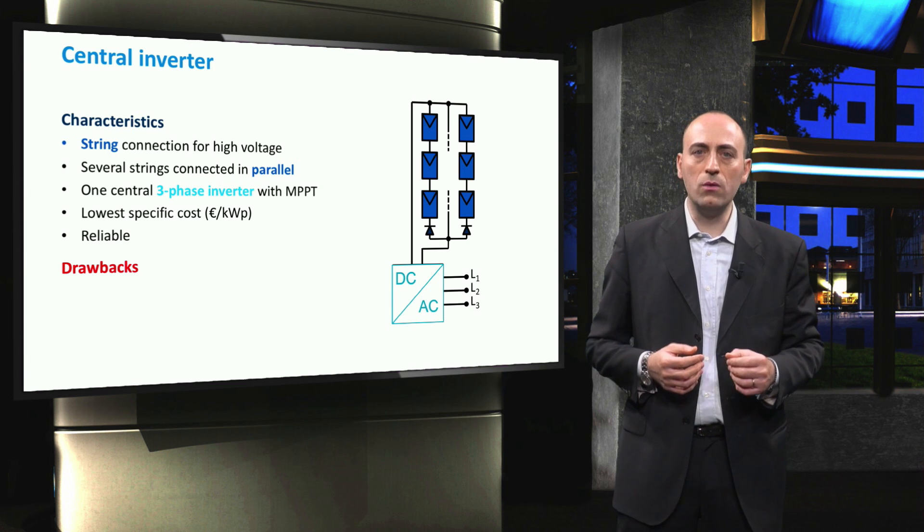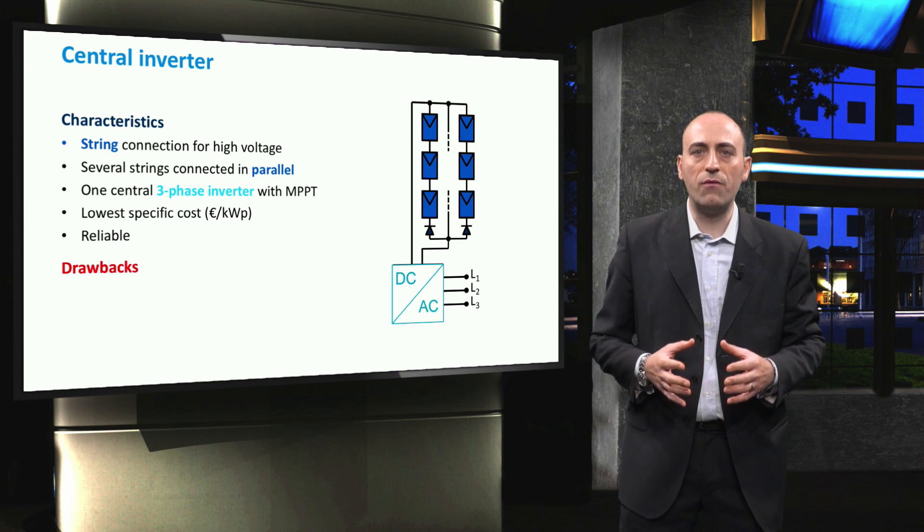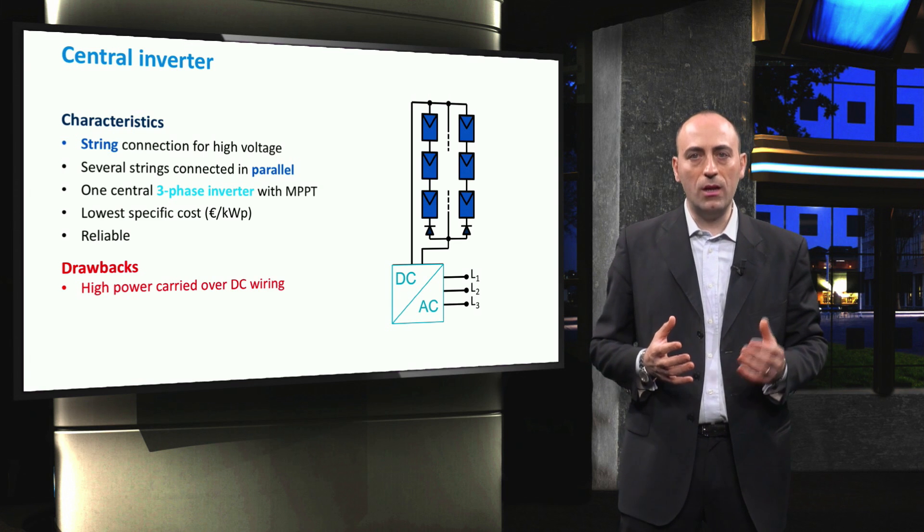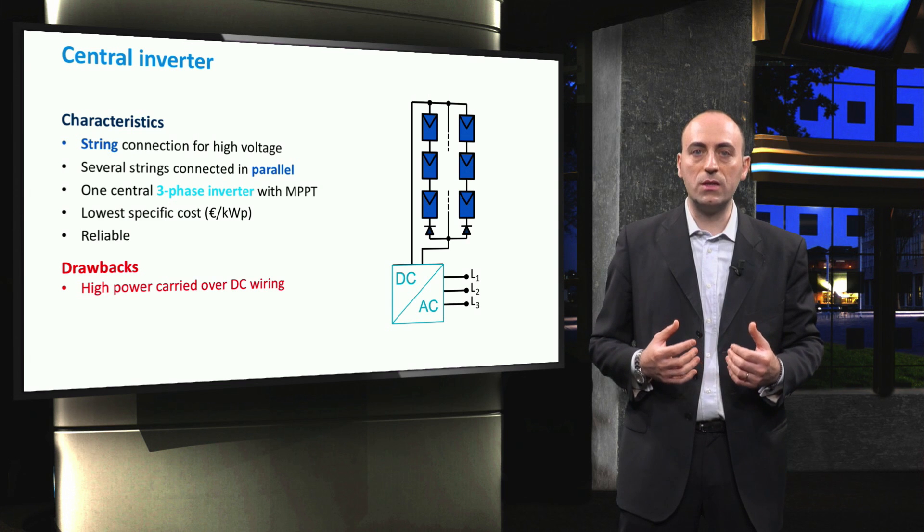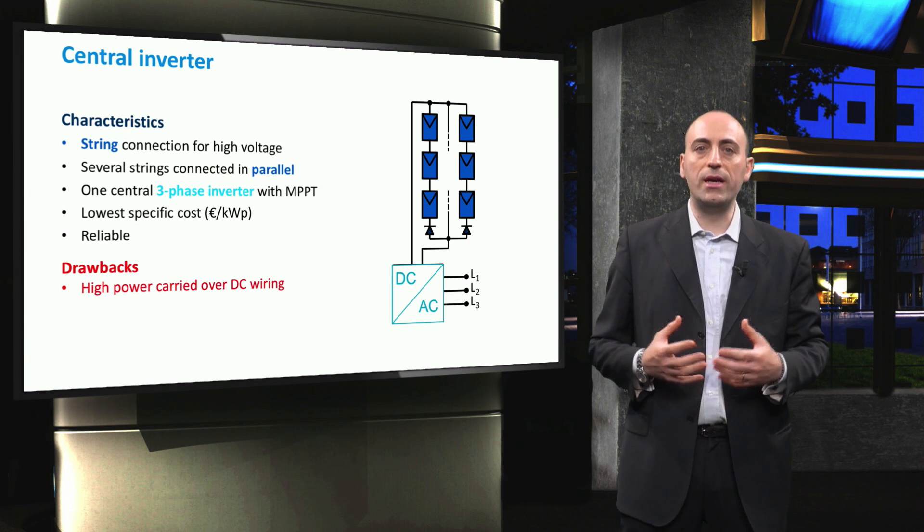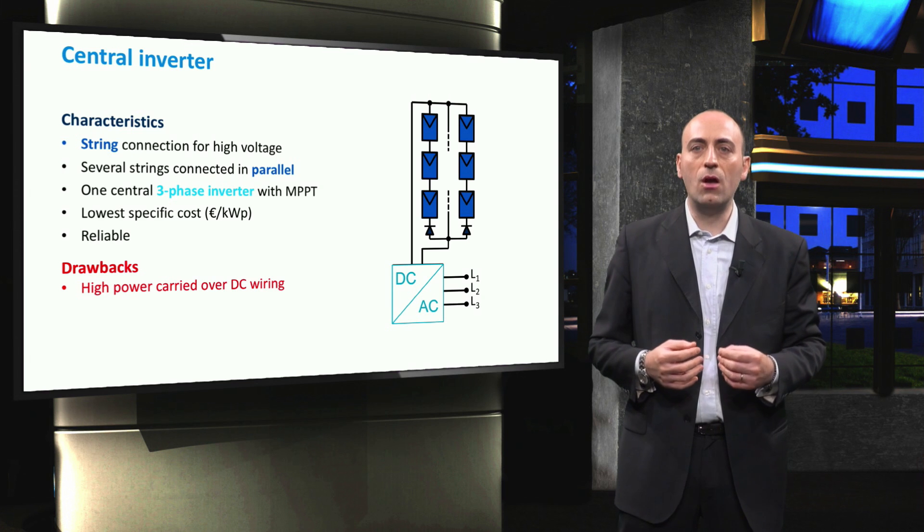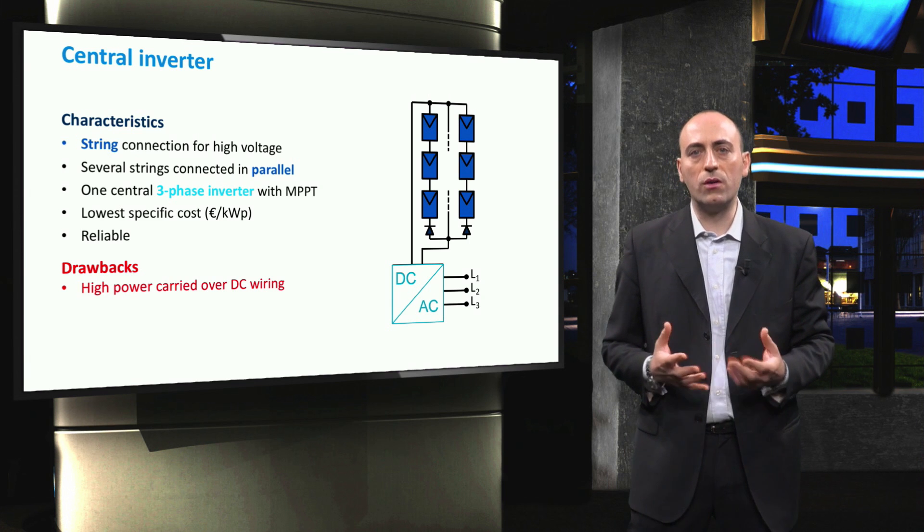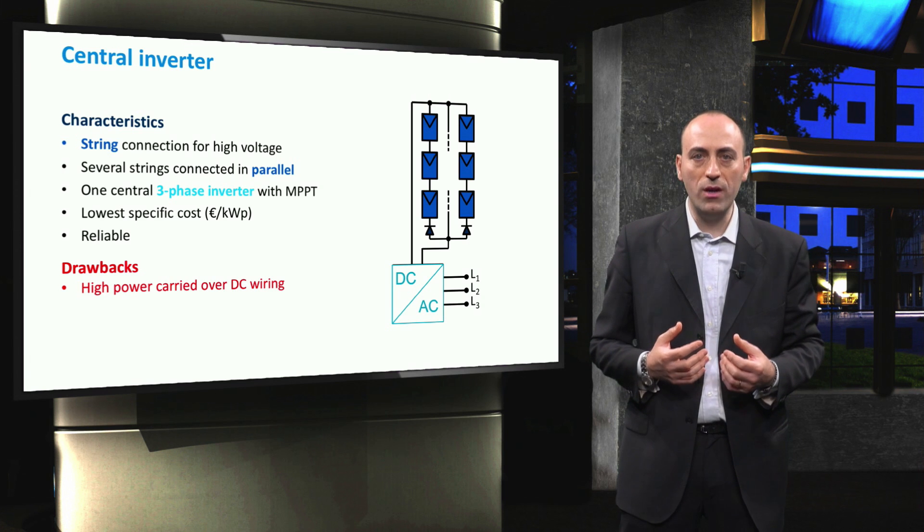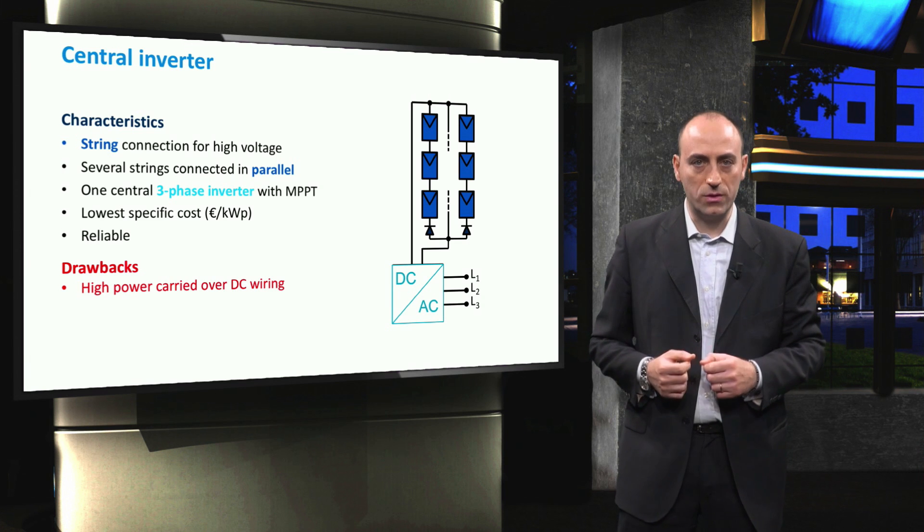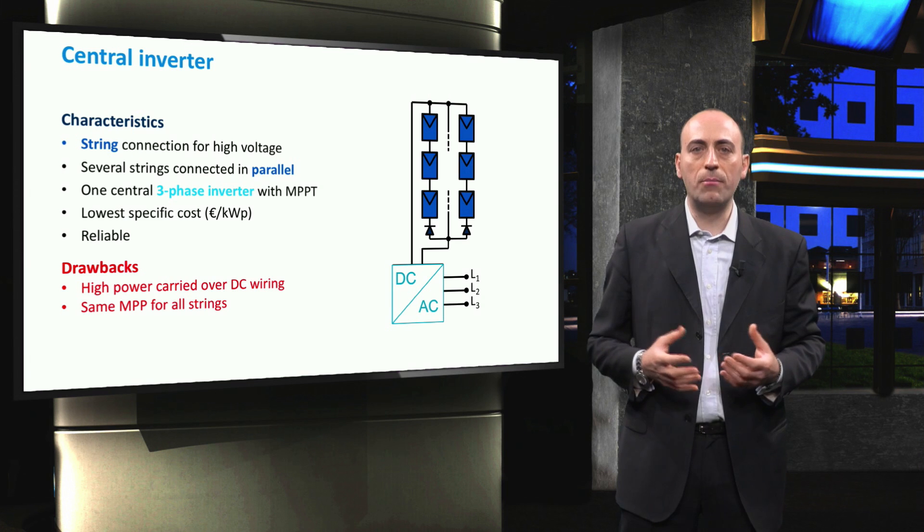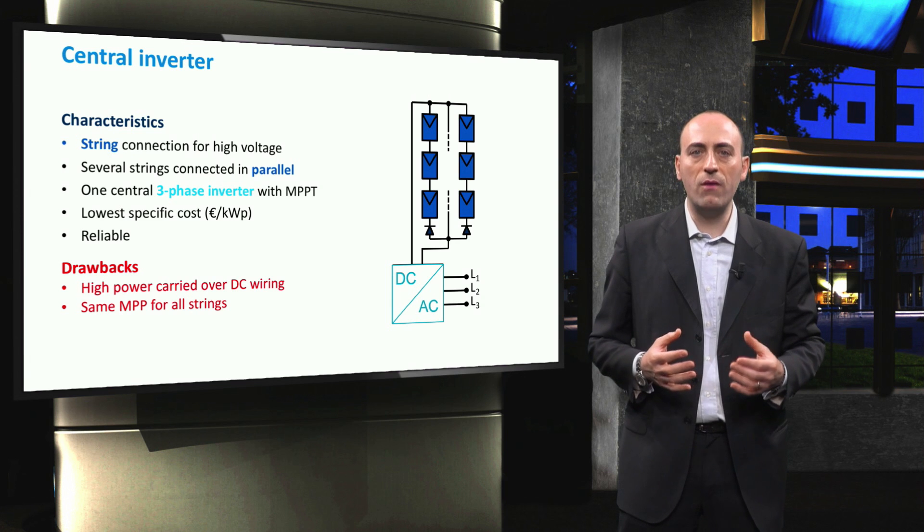In spite of their simplicity and low specific cost, central inverter systems suffer from some disadvantages. First, we have that due to the layout of the system, a large amount of power is carried over considerable distances using DC wiring. Therefore, the engineer has to carefully choose the type and thickness of DC wires, because this can cause safety issues related to fault DC currents, and the need for thick cables insulation and special circuit breakers can lead to a significant cost increase. Another drawback is that all strings are operated at the same power point, which might not match the maximum power point of each string, and then be problematic in a very large installation.